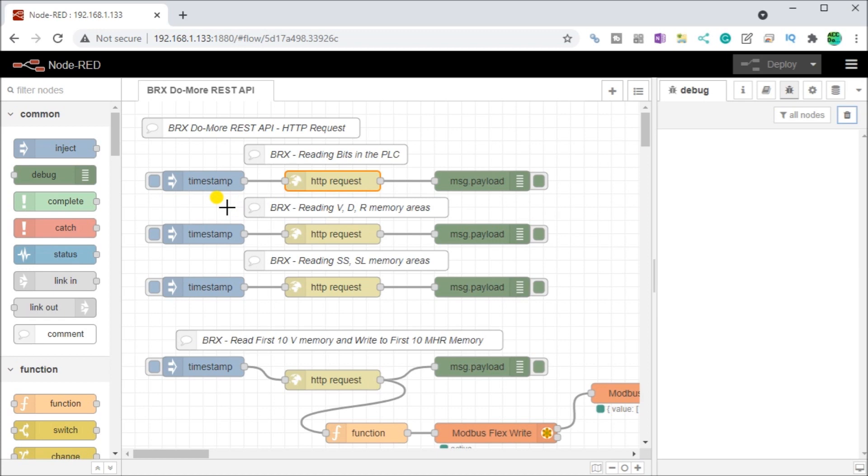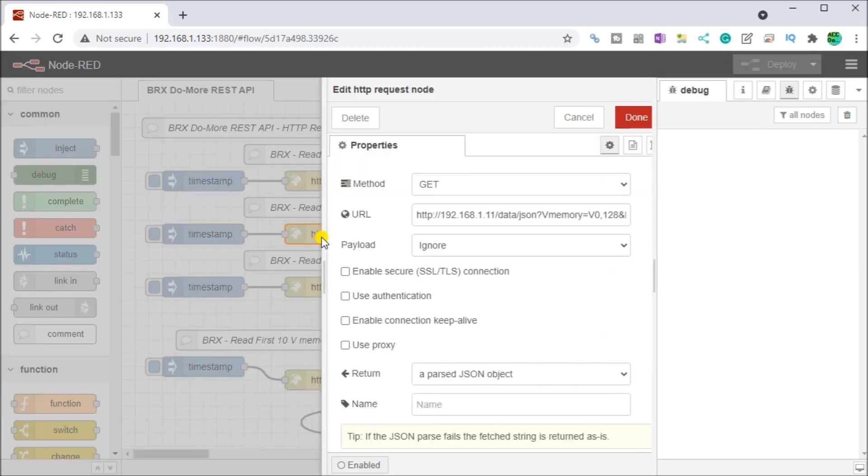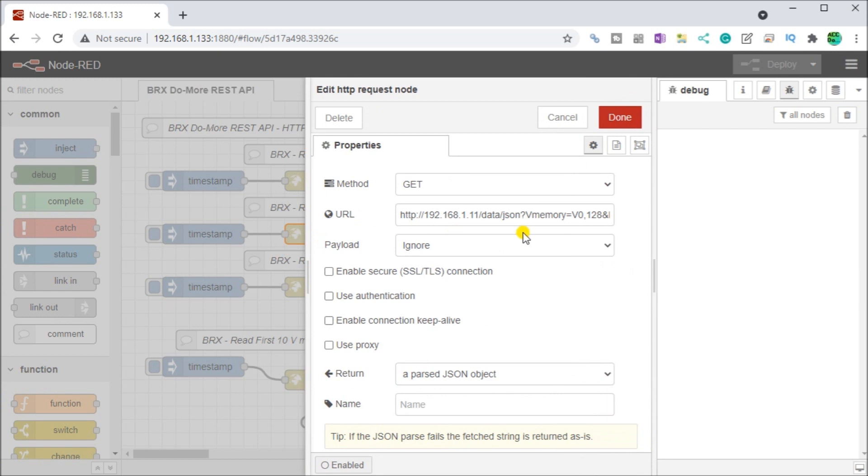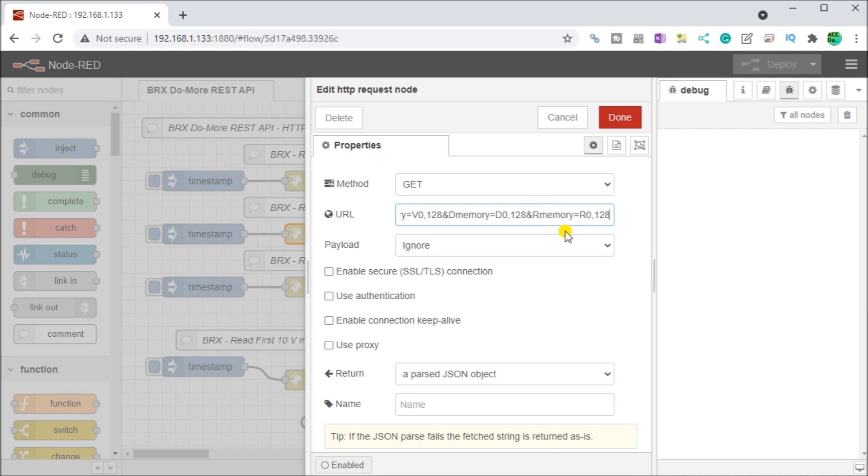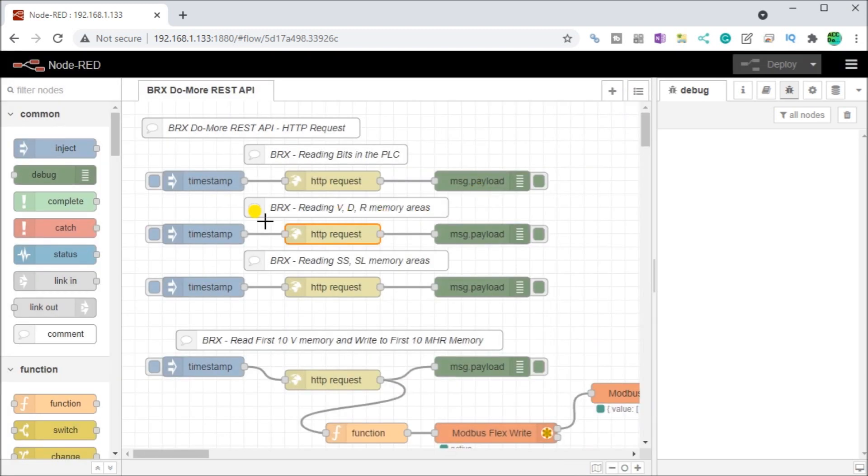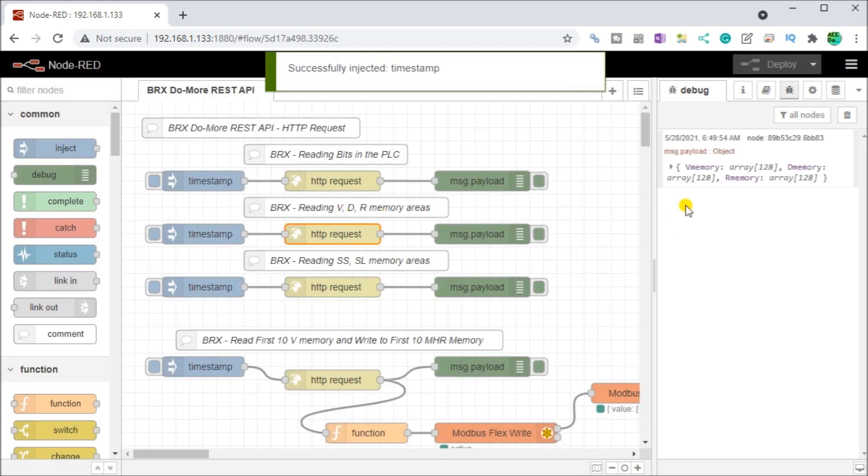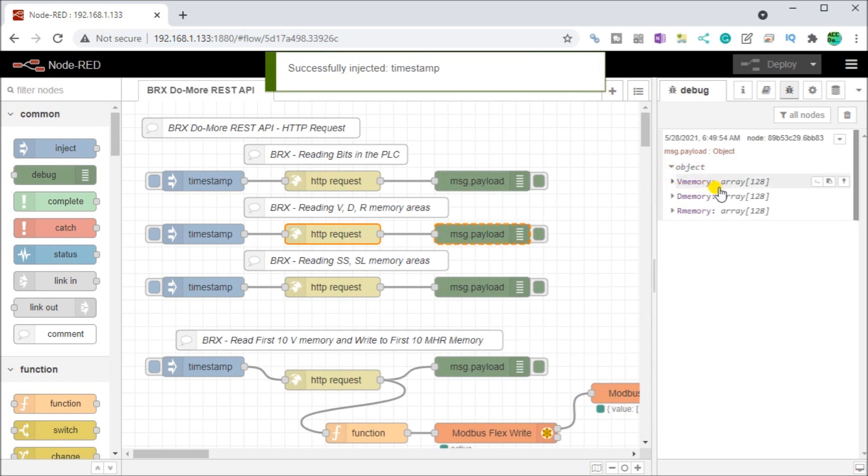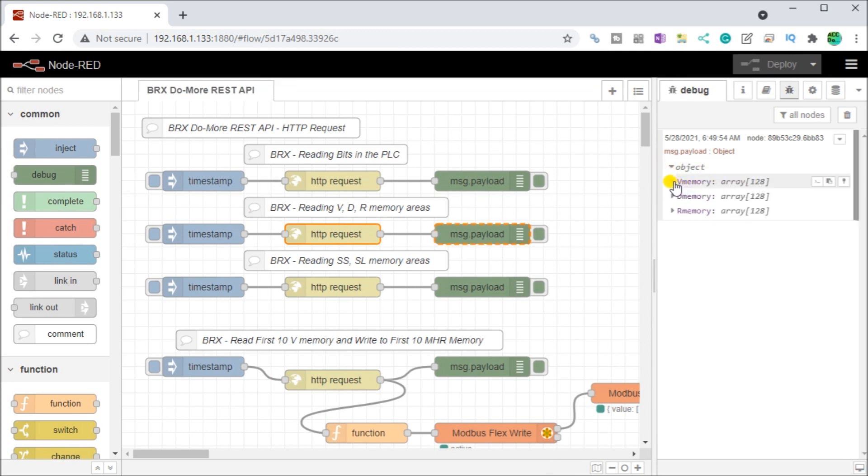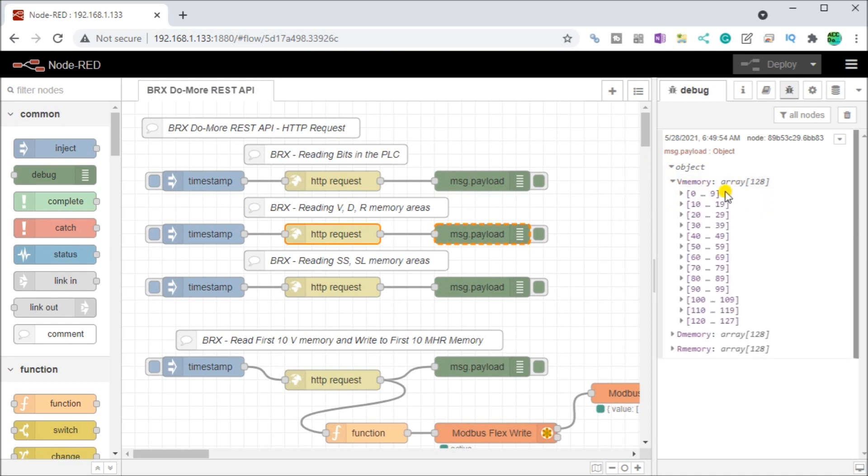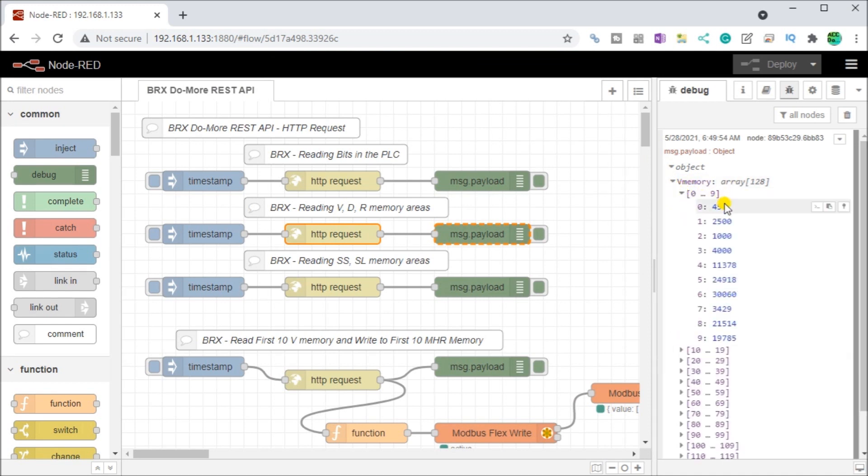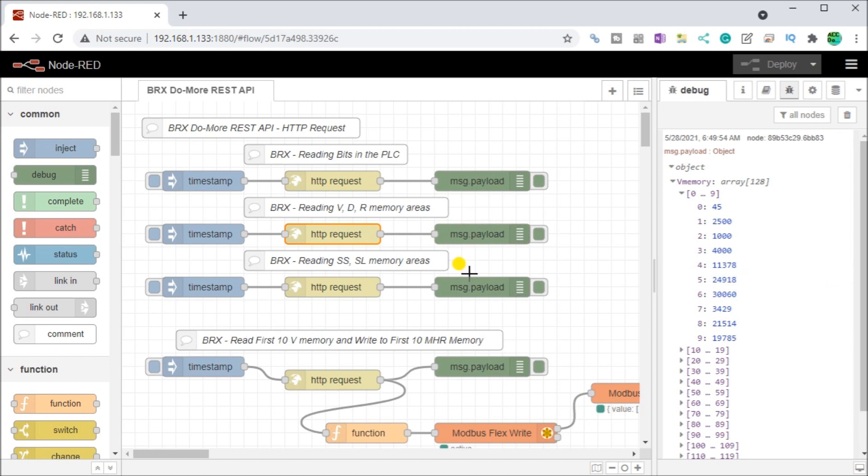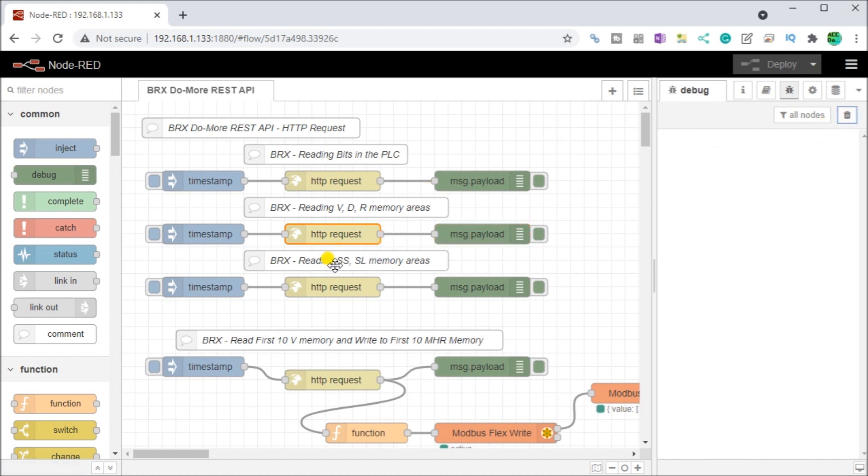Next, what you can do is we can read any of the memory areas within the BRX controller. If we hit this request, this request will actually bring back my V memory and 128 of them, my D memory or double memory and my real memory or real values. Let's try that. It will hit the inject node. And again, you can see that we have our arrays coming back in a JSON format. Our V memories are right here, 0 to 10, and there's my parameters for those. So you can read a lot of information very quickly out of this controller using the HTTP request.